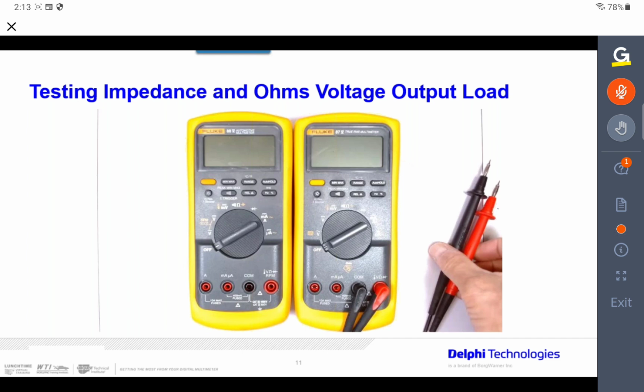Your meter needs to be 10 mega ohms impedance. The reason we need that is the high resistance of the meter. Your meter is going to flow voltage through the meter. If it's higher resistance in the meter, that means it will not pull that much voltage from the circuit it's working on. If I have 1 mega ohm, it will pull voltage from the circuit and affect my readings. It will actually affect the circuit.